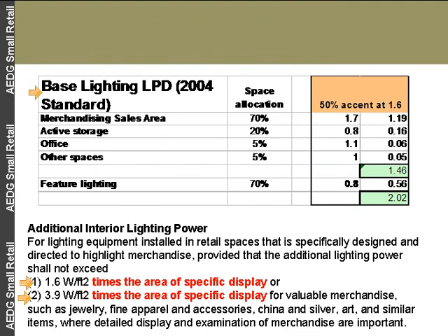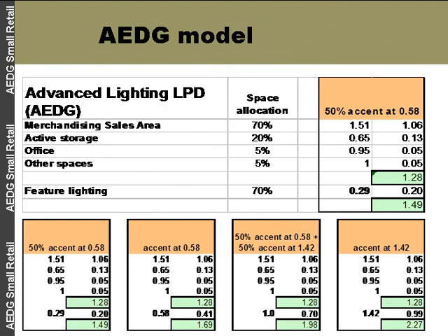And so here we've taken that new number, which is using ceramic metal halide, to get to that same scenario of the 50%, the 100% at 0.58, and that number comes actually just from a mathematical equation of what was the efficiency of ceramic metal halide versus the efficiency of halogen IR technology.